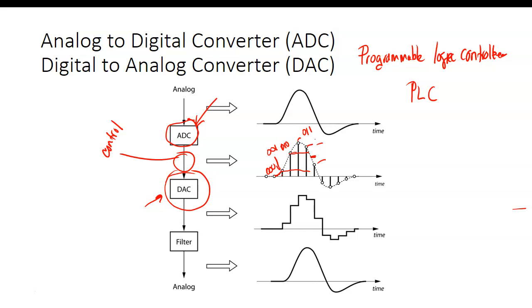It was all relay logic. You learned back in motor controls that we could do logic, right? And, or. When we went into the relay houses, one of them was probably as long as this room on number 4 galvanized line, just stacked full of relays. Most of those relays were in there for decision making, not to run a load. They were just there to do the ands, ors, nors, and exclusive ors, making sure everything is in the right place at the right time. All those control relays you look for in motor controls, that's what we replaced with programmable controllers.